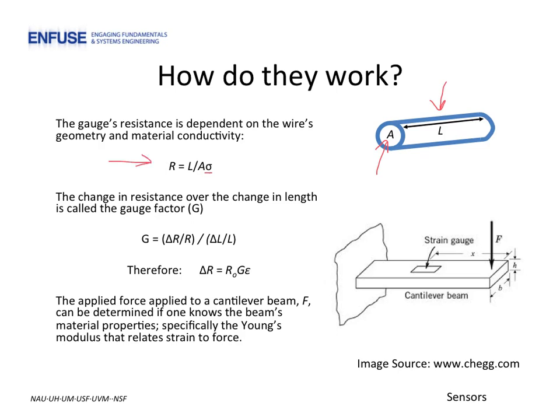When the bonded gauge undergoes tensile load, which causes it to be stretched, the overall length of the wire increases while the cross-sectional area decreases, as the volume must stay constant. The end result is that the resistance increases under tensile forces. Under compressive forces, the wire shortens and becomes thicker, and the resistance drops.